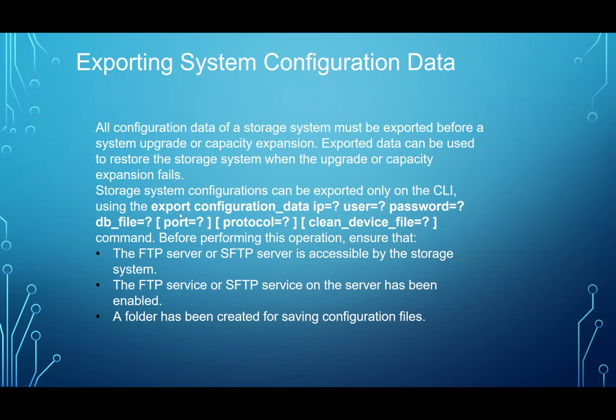I put the command here as well, and you must also know that this export of the configuration file only works in combination with an FTP or SFTP server. So either the customer has an FTP or SFTP server configured for this kind of job, or you can use third-party software that has an emulator for a virtual file server on your PC. And then you would be able to download this configuration file locally.